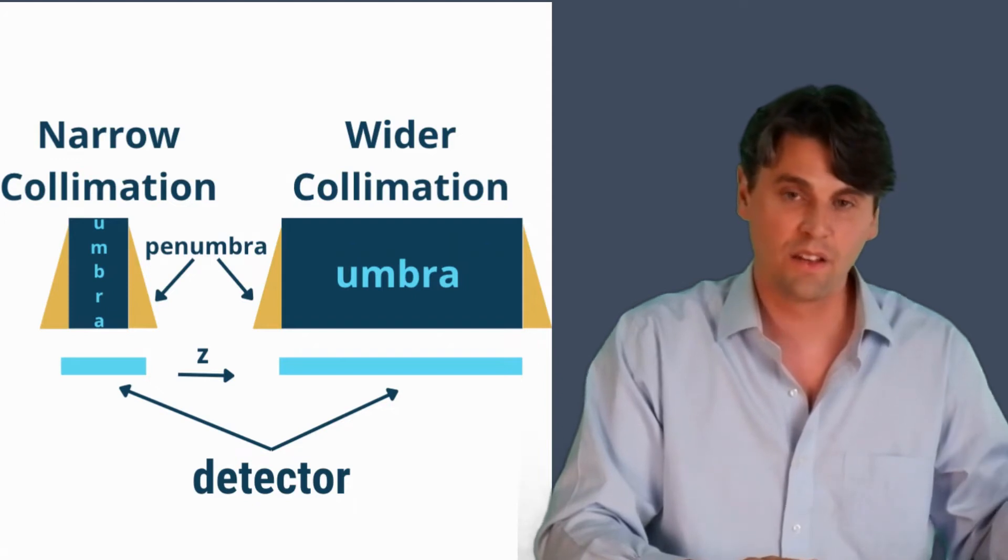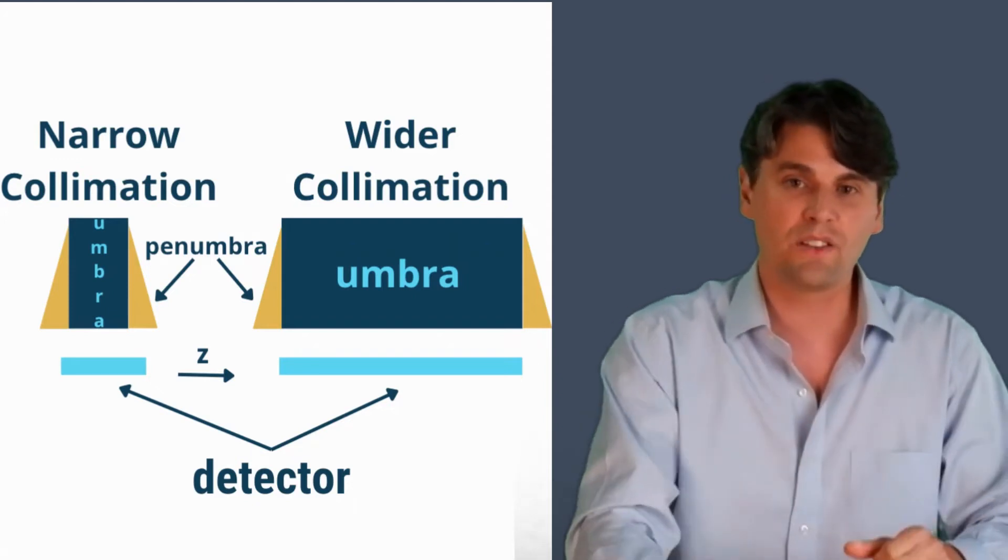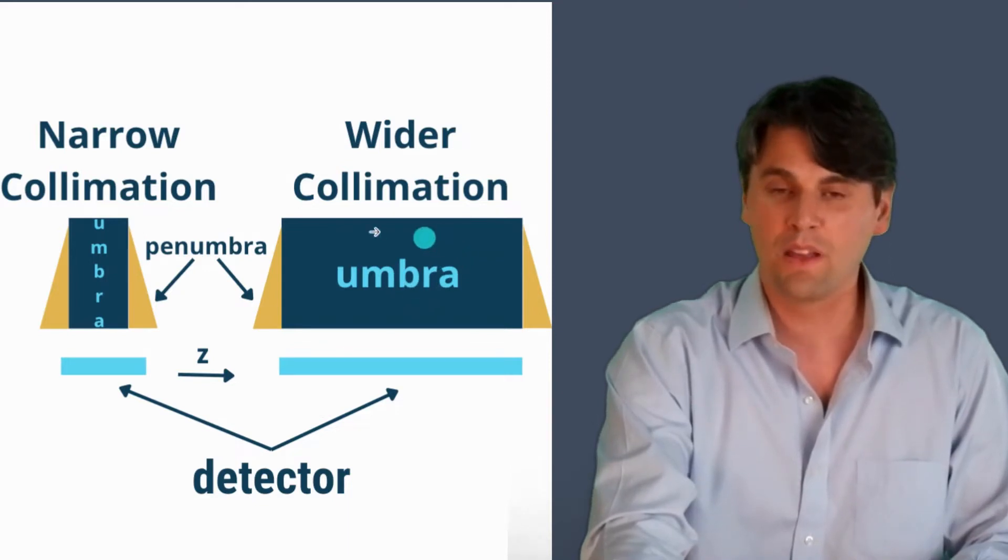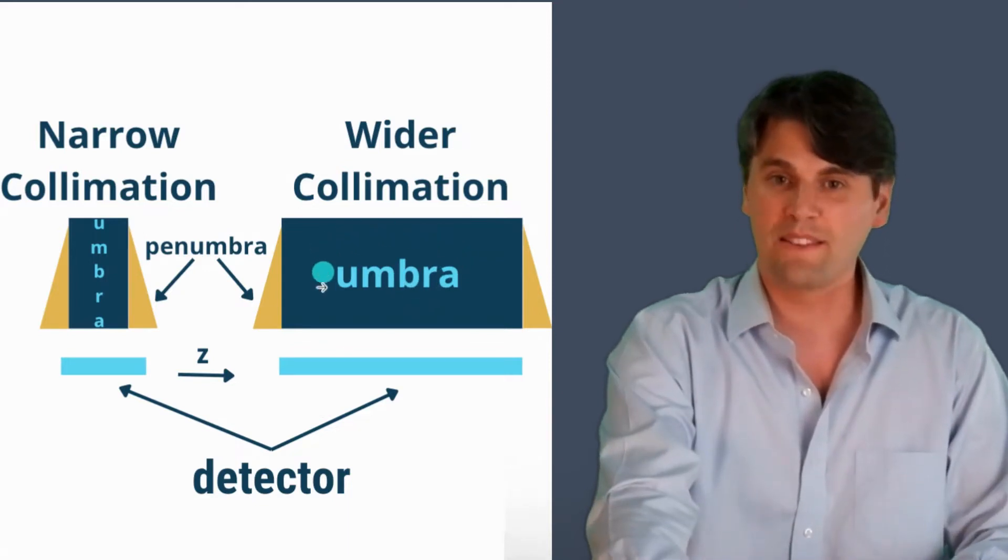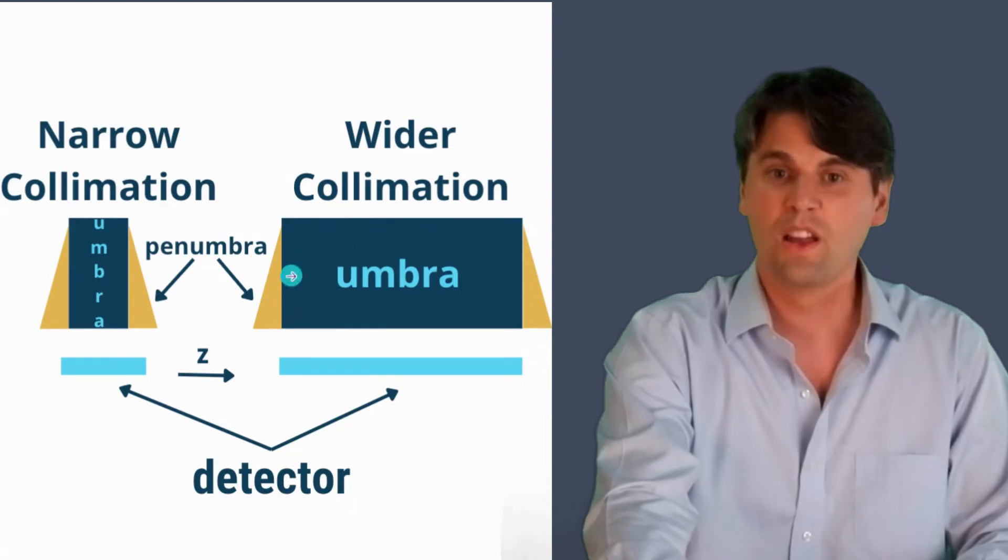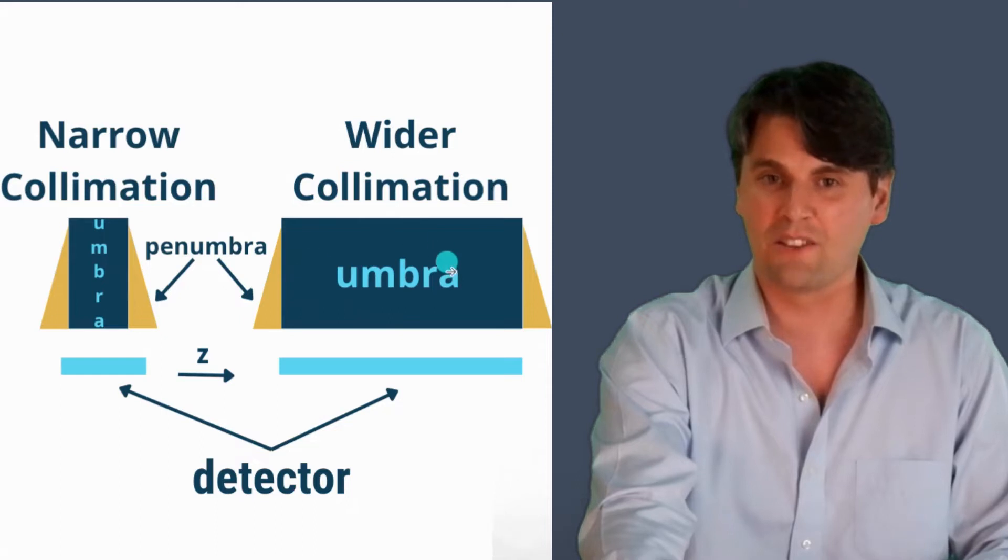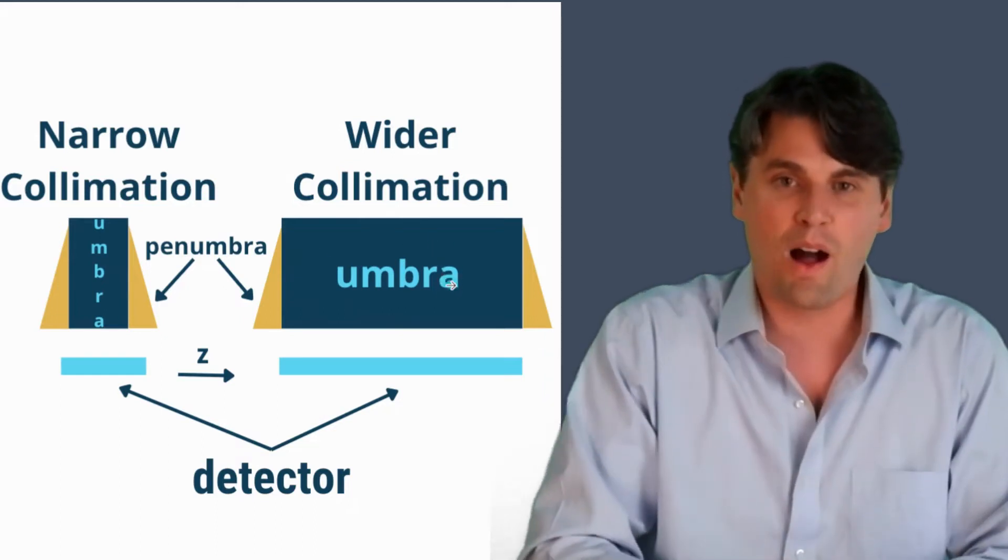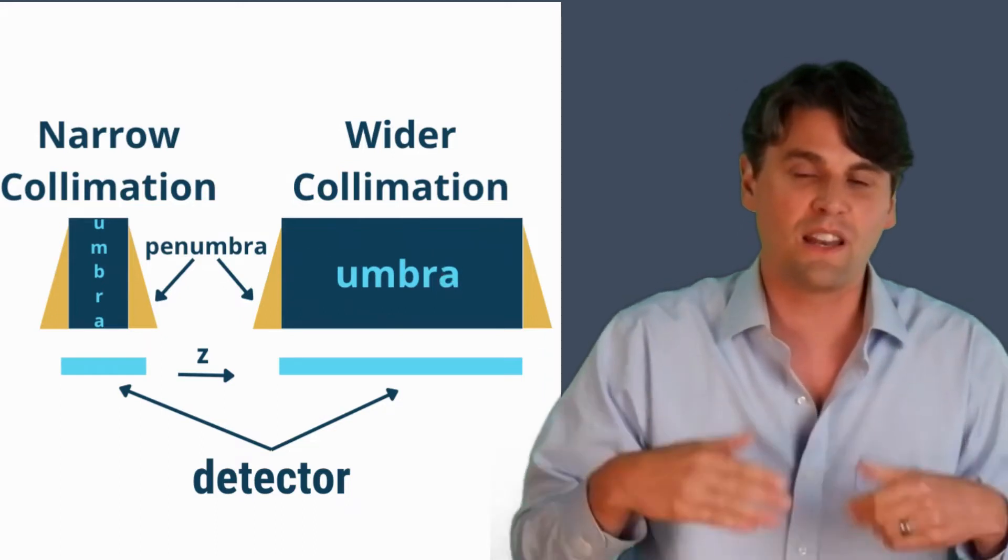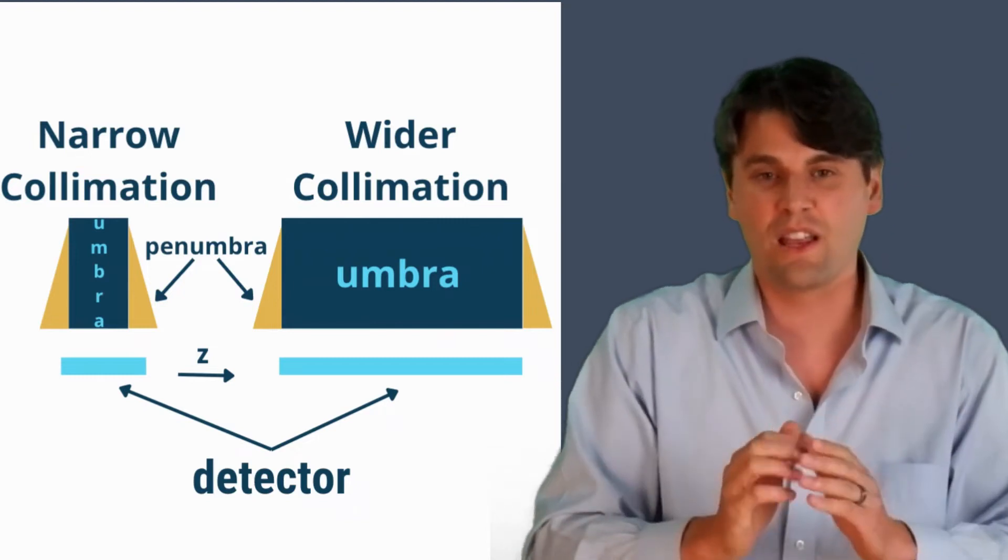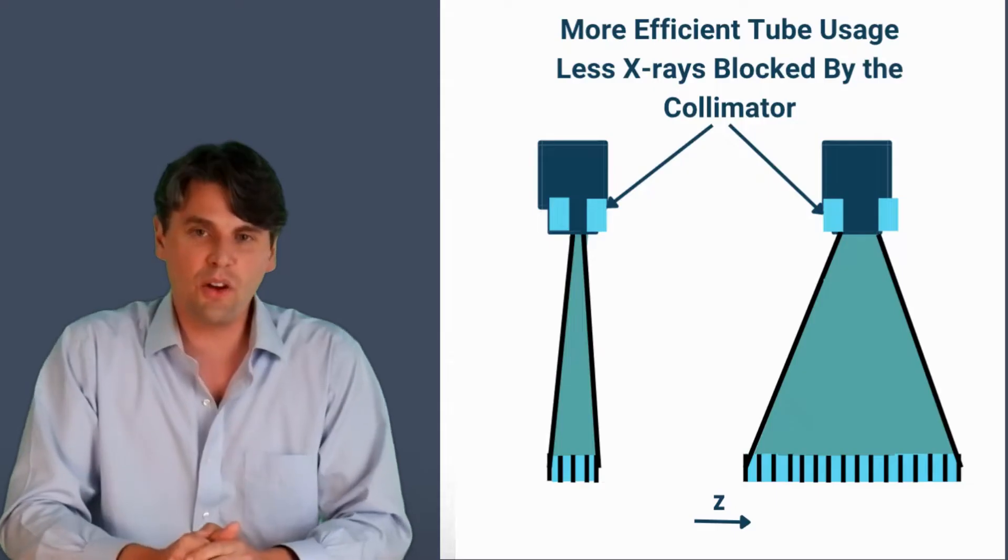So the wider collimation case is more efficient because every time you have this amount of wasted radiation in the penumbra, you're getting a much wider region of good radiation in the umbra. This is why the wider collimation has a higher what we call geometric efficiency than the very narrow collimations. There's also an efficiency gain from the standpoint of the tube heating.